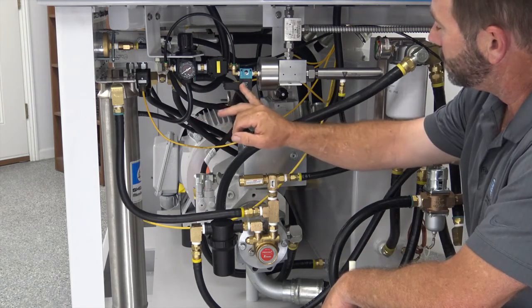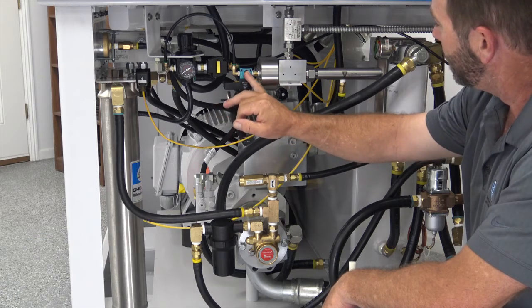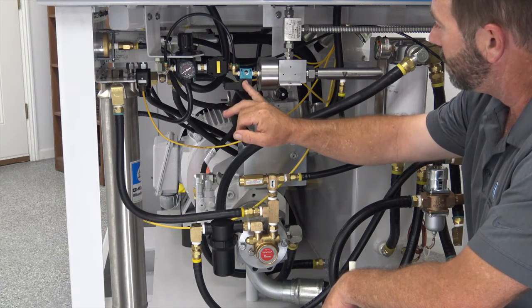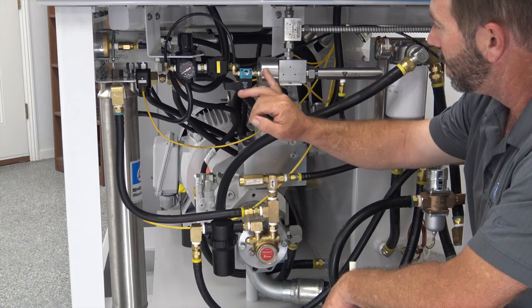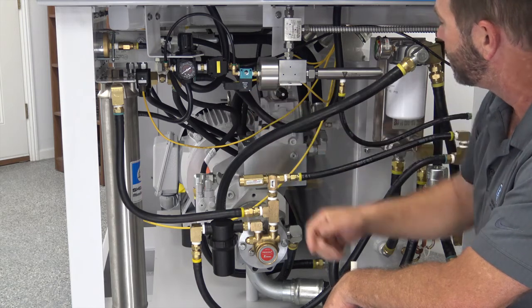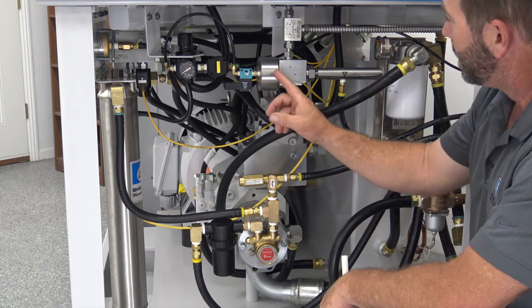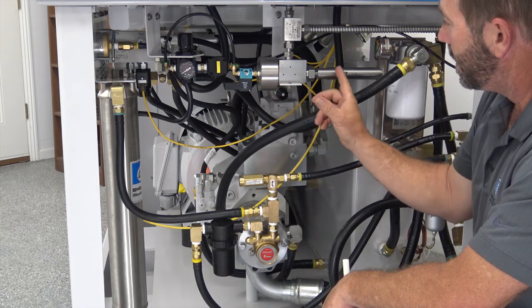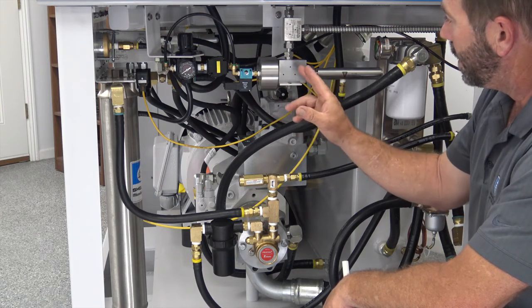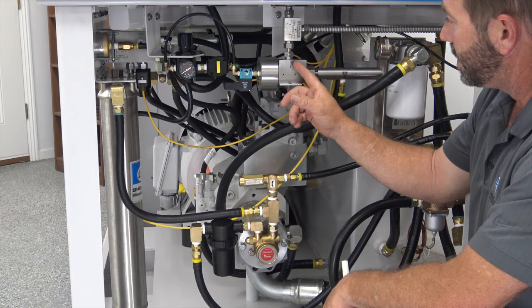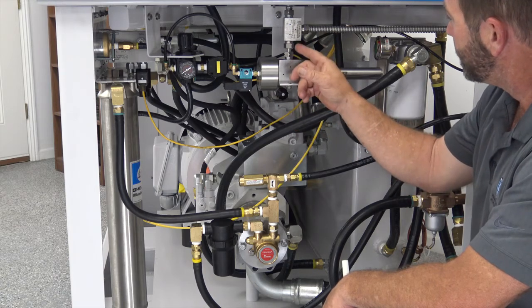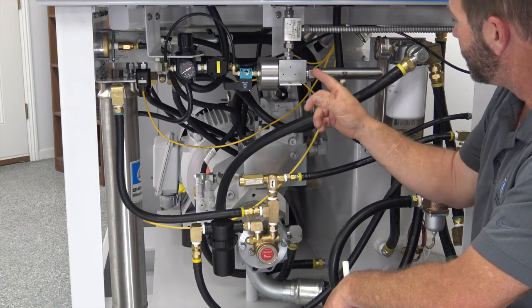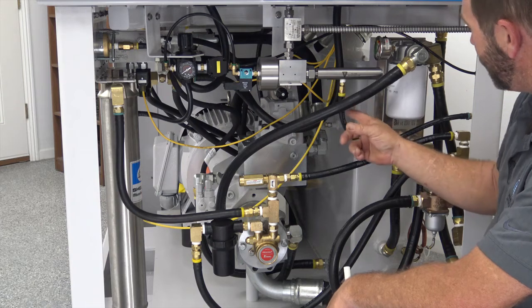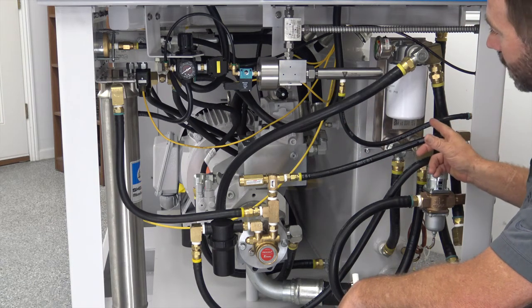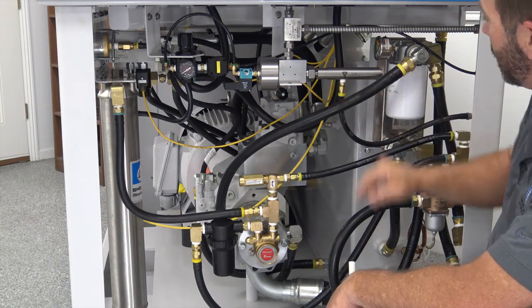Working your way across, this is your pneumatic solenoid valve. Basically it controls the opening and closing of the air going into the actuator on this valve. This is your normally open valve assembly, and like I said, when it opens, it allows the water to escape the system through this catcher tube assembly that's on the end, and it comes back into your inlet water. So that's how that works.